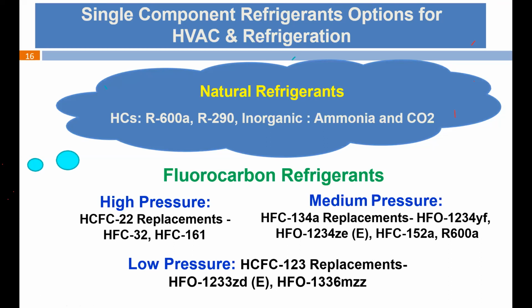What is hydrofluoroolefin? We have talked about HFC and HCFC, where if you see the bonding of the carbon, there are 4 bonds of carbon, and in all the Freon categories, CFC, HCFC and HFC, the bonding is single. Each C has 4 bonds, with single bonding. But in the case of HFO, this is an unsaturated refrigerant. They have at least 1 double bond between the carbon atoms, so the carbons are connected by 2 bonds, and the left-over bonds are only 2. These are all unsaturated refrigerants, but they have very good thermodynamic properties, especially low GWP. So you can say these HFO refrigerants, and blends of HFO and HFC, are the future refrigerants.